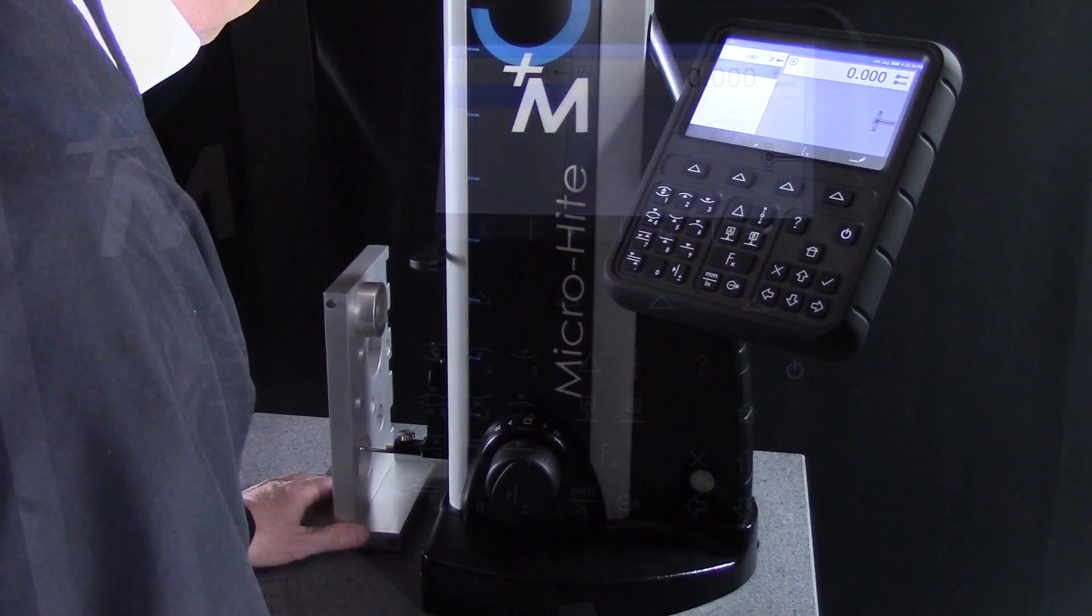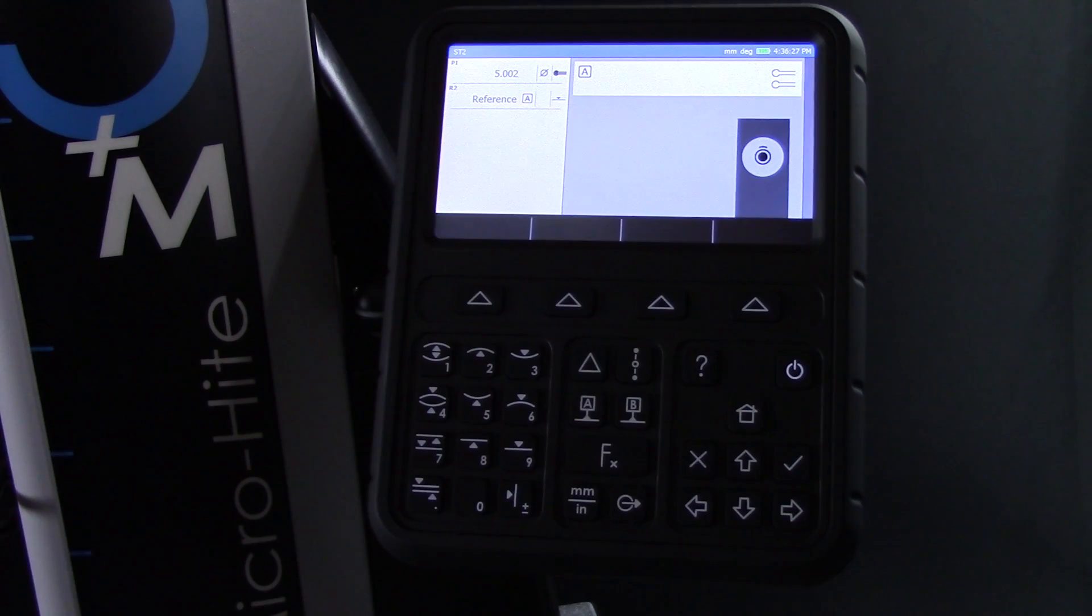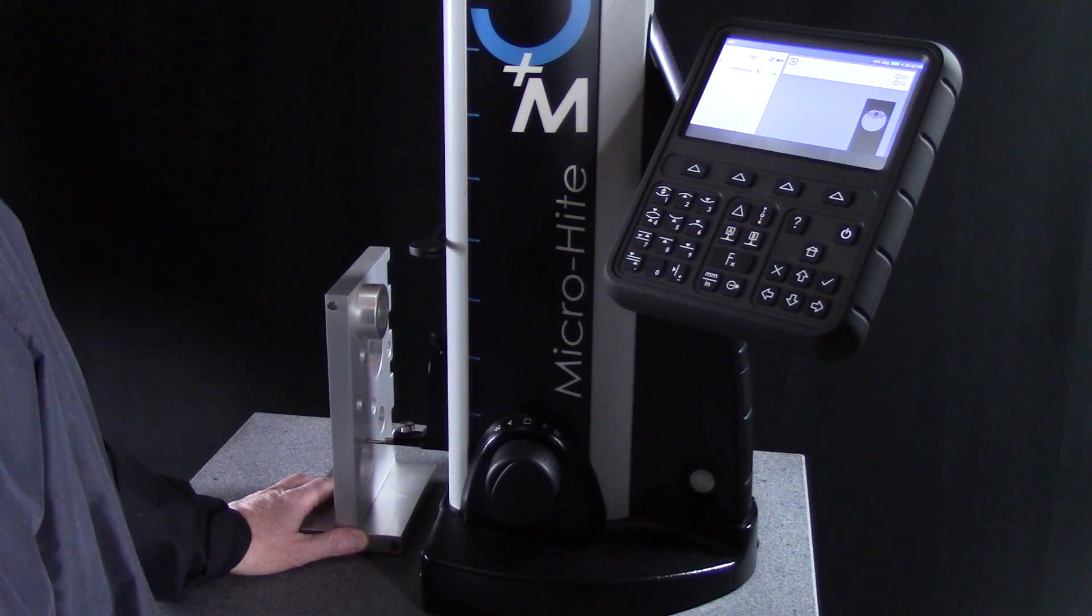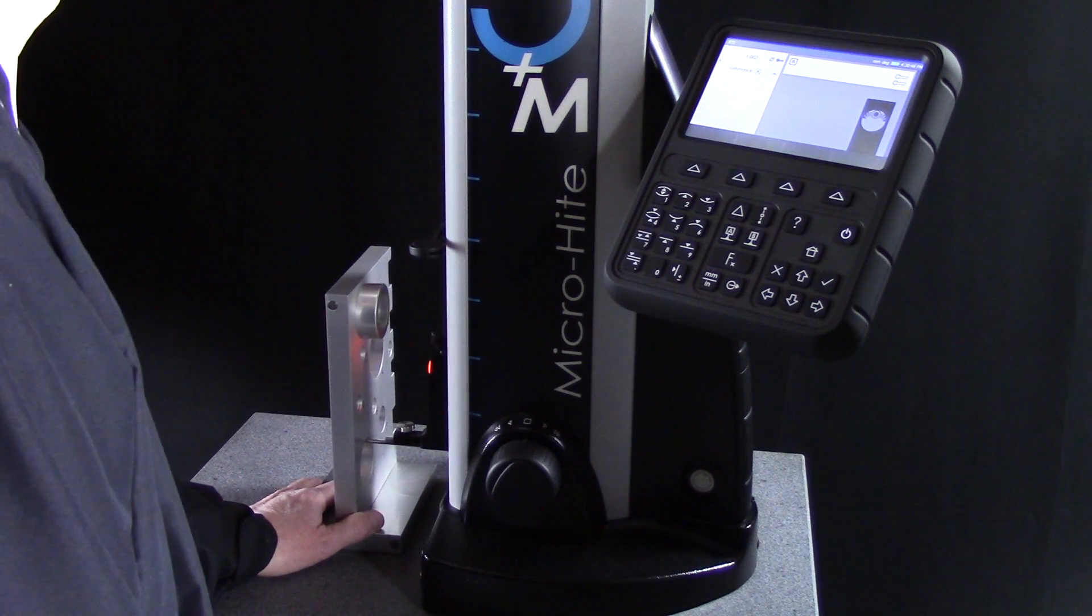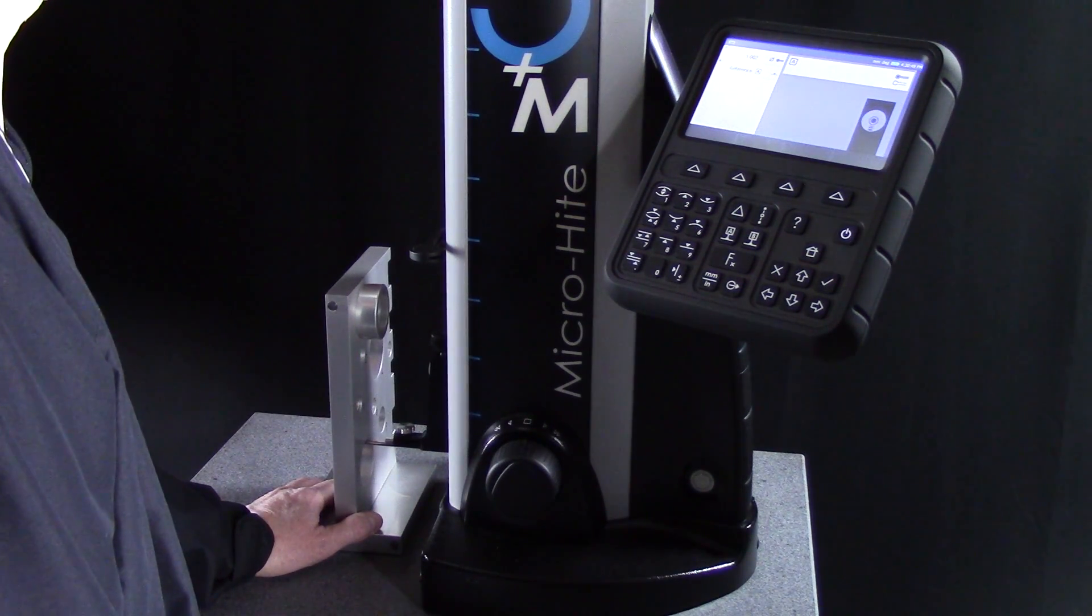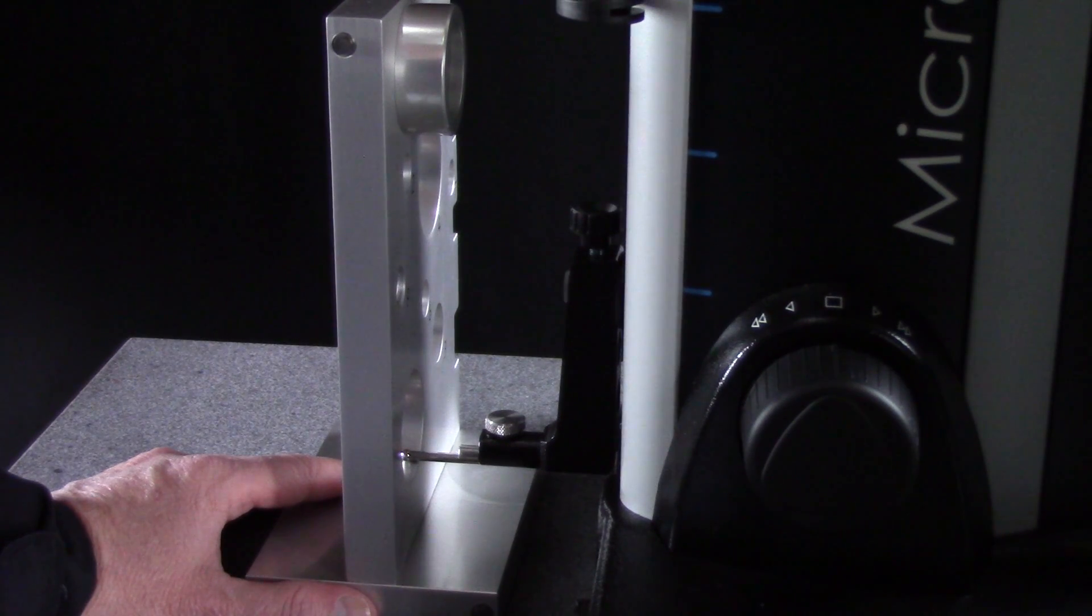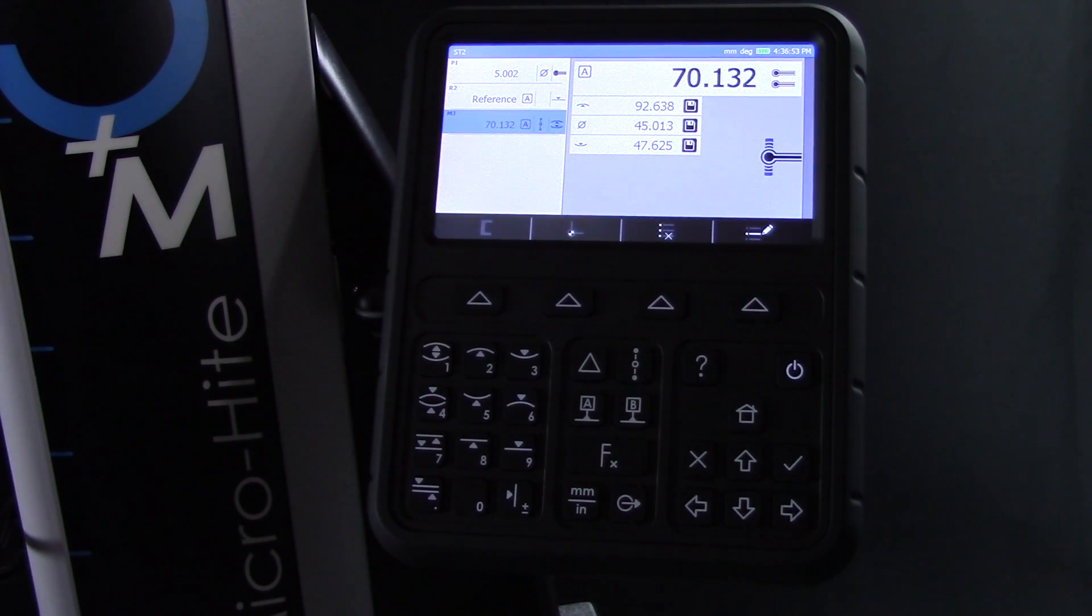Now I'll measure the top and bottom of this bore by selecting the automatic bore measurement button from the measurement zone on the keypad. I'll sweep each surface so that the gauge can determine the high and low point. When the measuring process is complete, the centerline measurement is displayed.